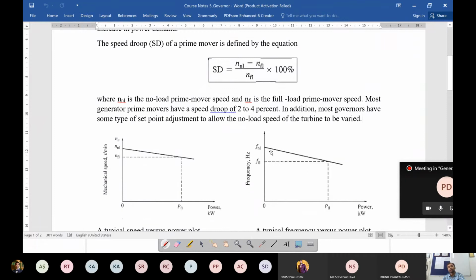So it's a very real-time operation. It is not done manually. It is not done by hand. The governor has a control mechanism where it keeps sensing the operating frequency and how much the power demand is. Accordingly, it keeps adjusting the operating frequency. This is a real-time thing, and this governor mechanism is the control mechanism which takes care of the fact that in the operation of a real-time power plant, the operating frequency has to be kept constant.